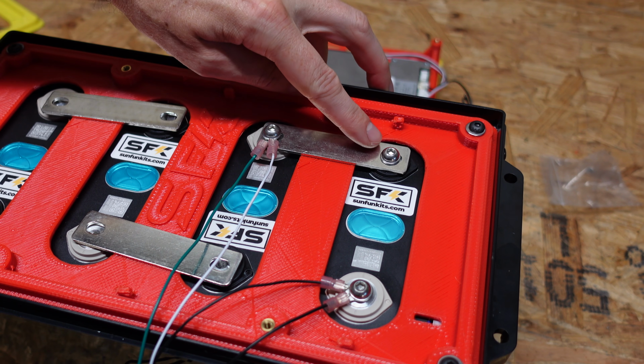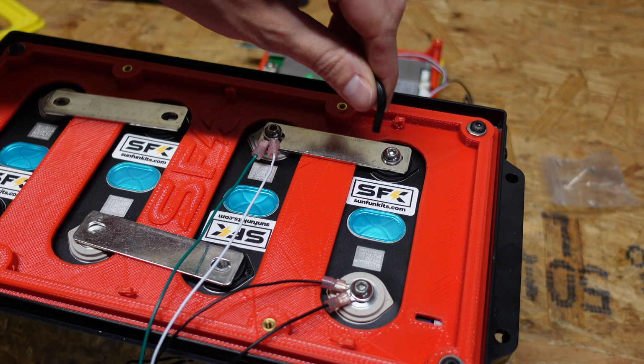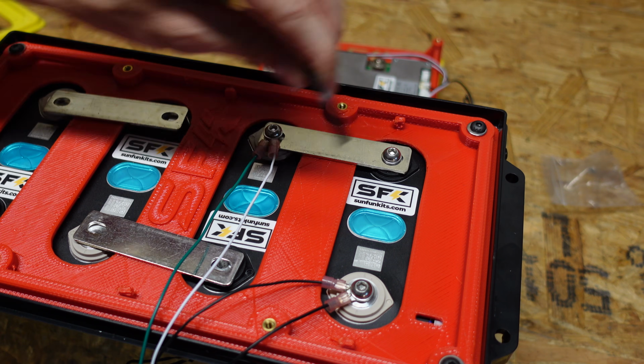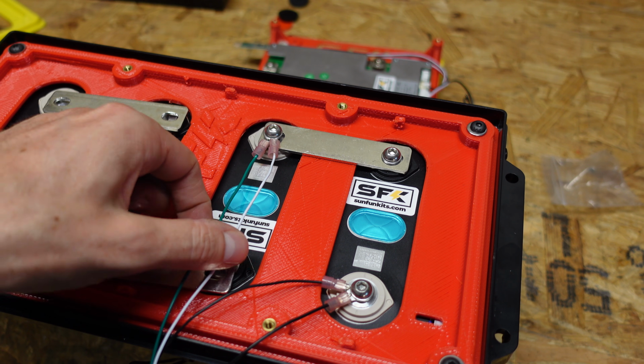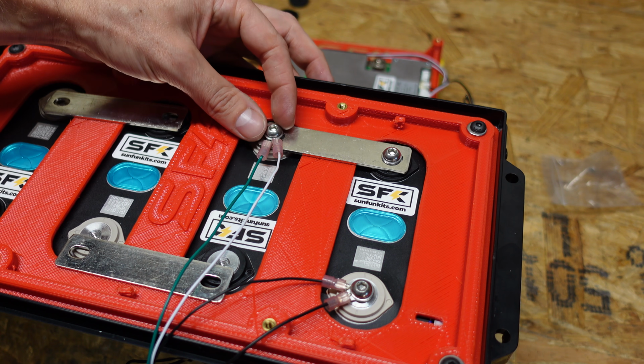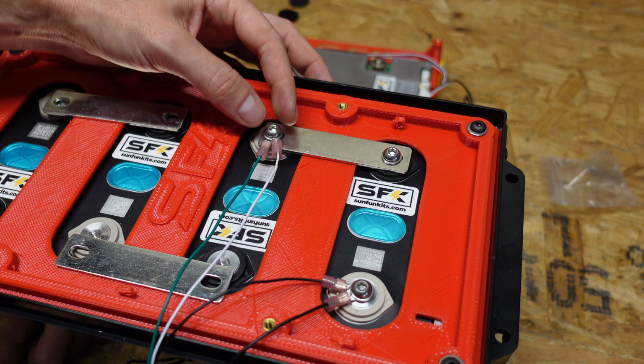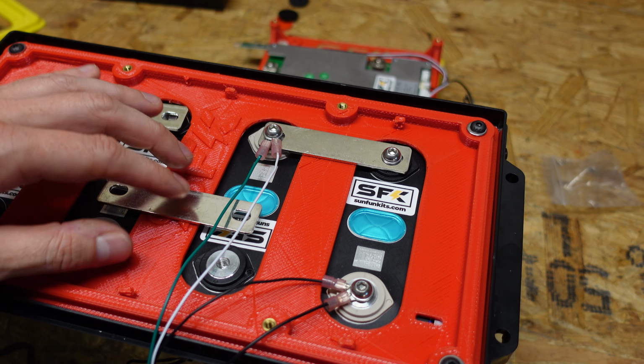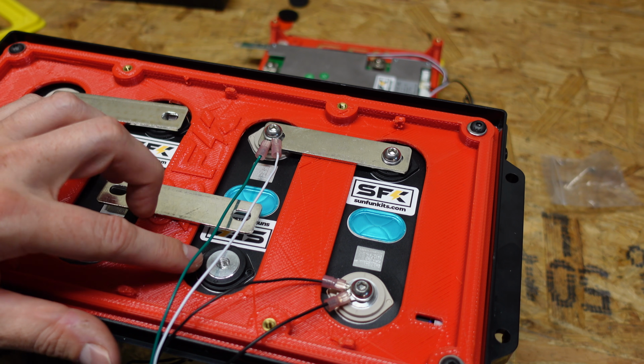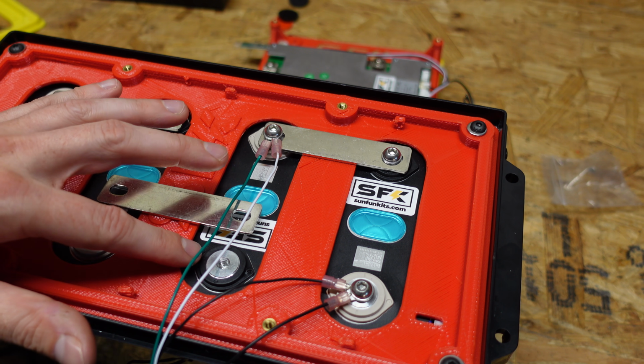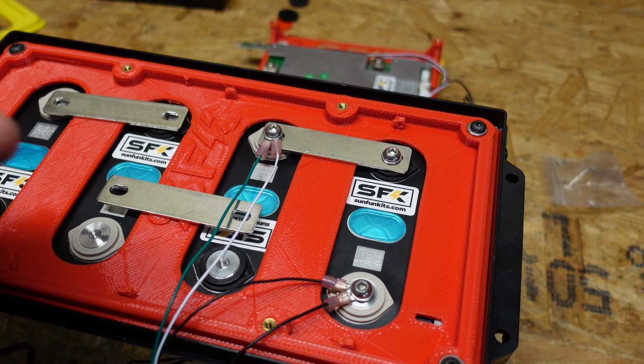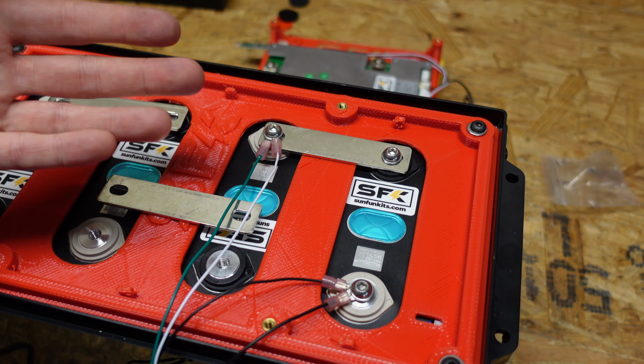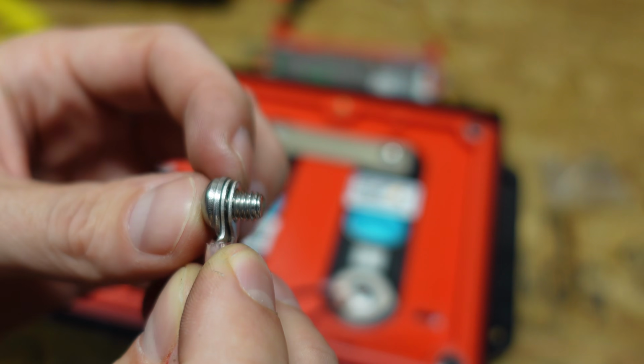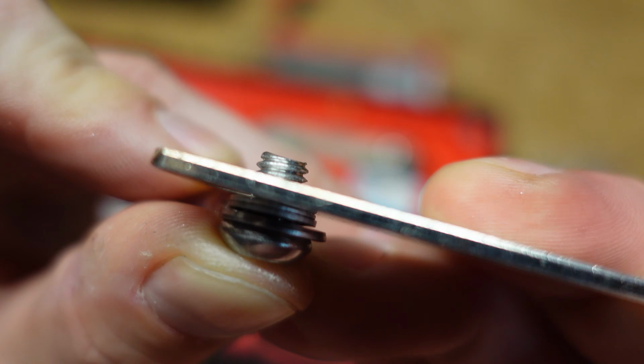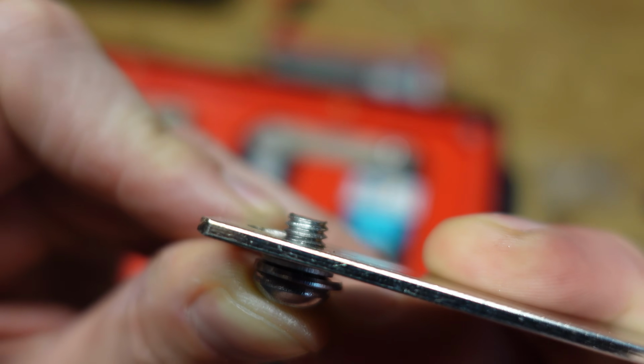When I tighten down this bolt on the far right, it feels really good, nice and tight, but this one on the left with 2 ring terminals feels like it's going to strip as I tighten it down. These EVE cells have aluminum posts and aluminum threads, and it's very easy to strip them out. I don't want to do that because once stripped, these cells are ruined with no way to use them after that. You can see once I pile on 2 ring terminals, the washer, and then the bus bar, there are very few threads left to actually grab into the cell.